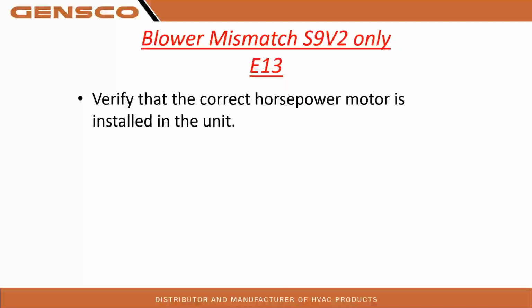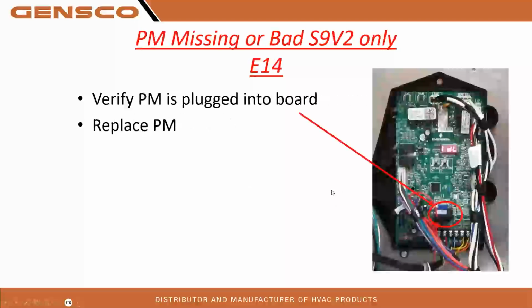So that personality module is programmed for a 3/4 horse, whatever. And that motor has to be willing to accept that packeted information, right? So it's a direct call out from that module there. So it could be, if you're trying to make something work, that the motor can't take that programming, or it's the wrong programming for that motor.